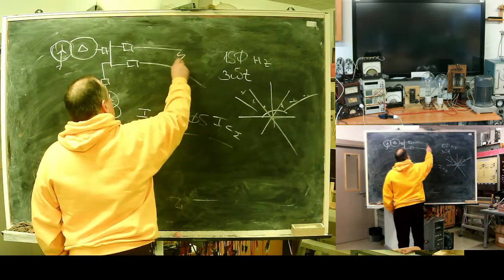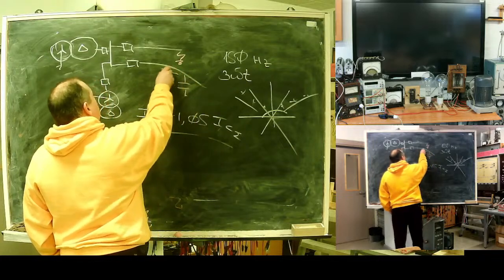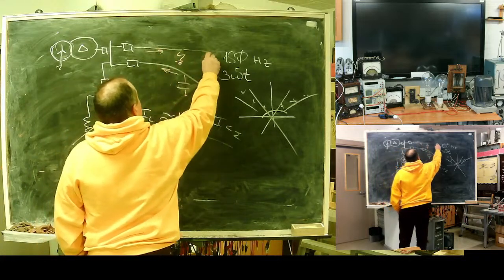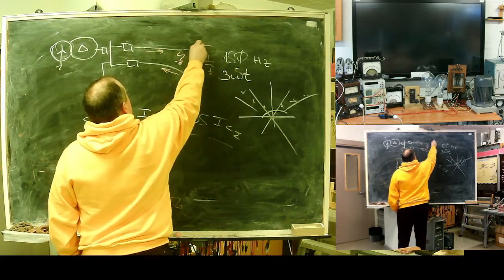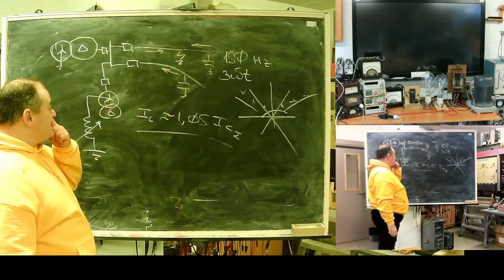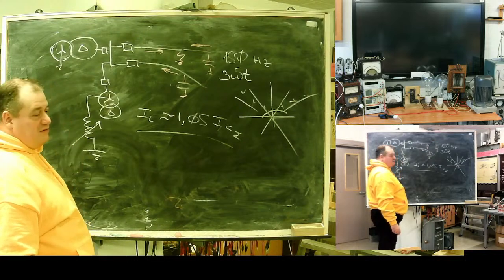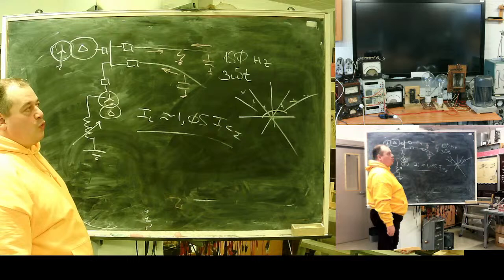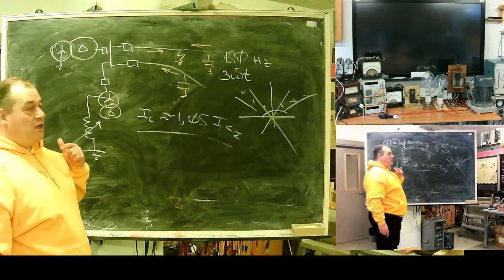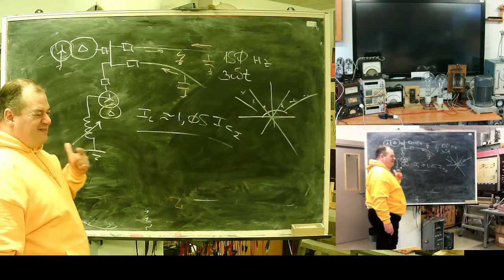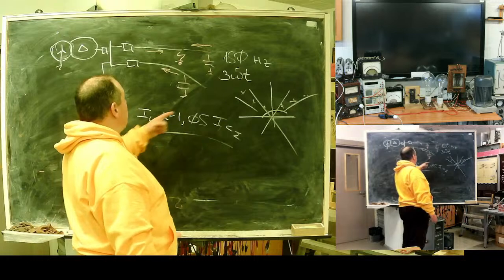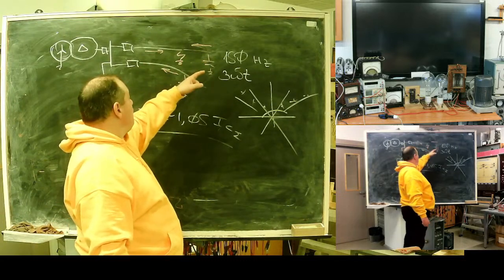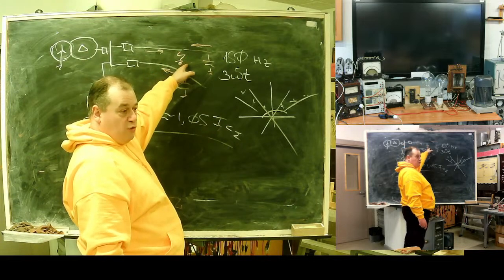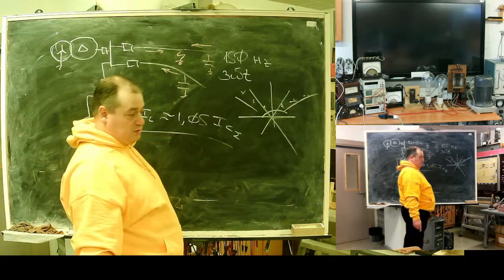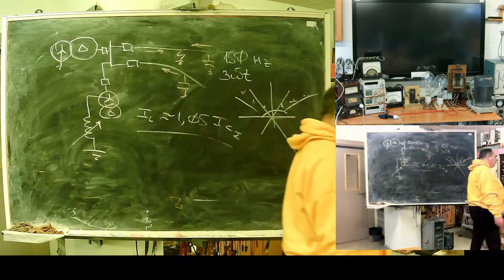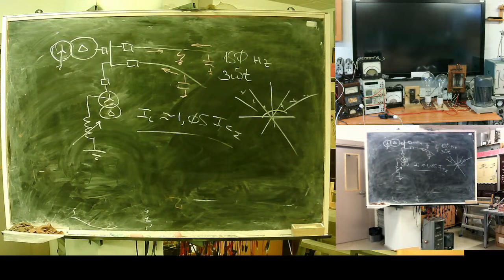Because the whole network capacity discharges to the fault place, you need a wide frequency sensor able to operate at all frequencies. Actually, you need to calculate the amount of energy flowing through the line during discharge. Because all discharge occurs through the fault place, the strongest signal will be on the faulted line. But there is a problem because it's exponential and the signal is very low.